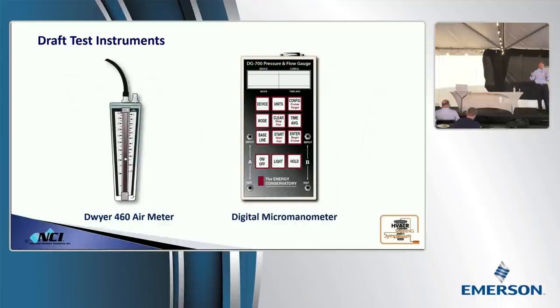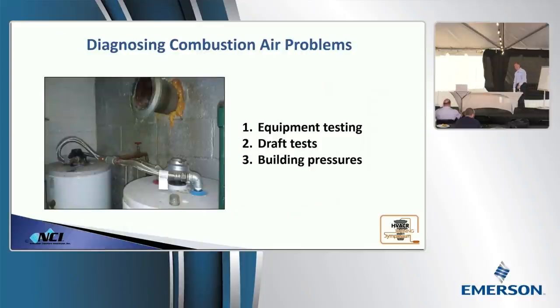This is why when we start to turn on fans, we start to change door positions. We're going to see what causes that ball to drop. Because that's the line in the sand that we've got to figure out that we need to fix. That's what we can't cross. You're also going to need a micromanometer, a high precision manometer, to measure building pressures, to see what's going on in the equipment and also in the building side of the duct system. Now, when you test, we're going to start with the equipment.